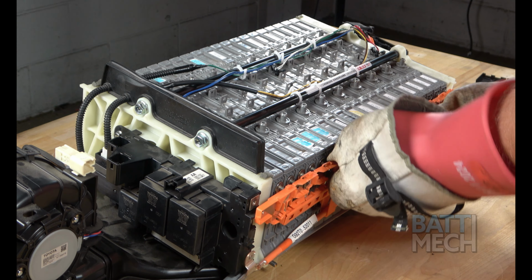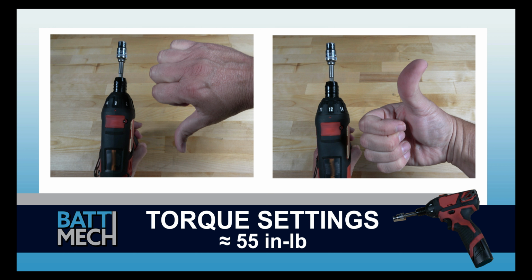Before you attach the wire harness using the new nuts supplied by BattMech, be sure your torque settings on your torque wrench are set to about 55 inch-pounds. If you don't follow these torque settings, you are likely to damage the terminals on the modules and will void your warranty. Never use max drill settings, and never use an impact wrench.